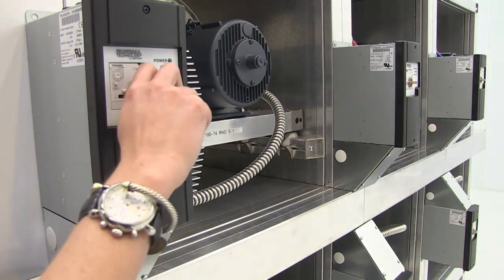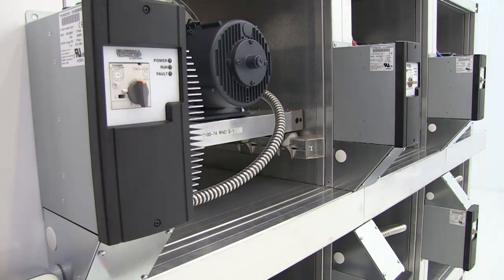Now it's time to commission your VFDs. Note that except for the VFD connected to the keypad, all VFDs must be powered OFF prior to commissioning. Only one VFD can be commissioned at a time. Turn on the VFD connected to the remote display.